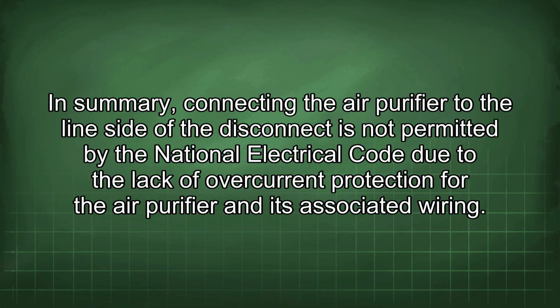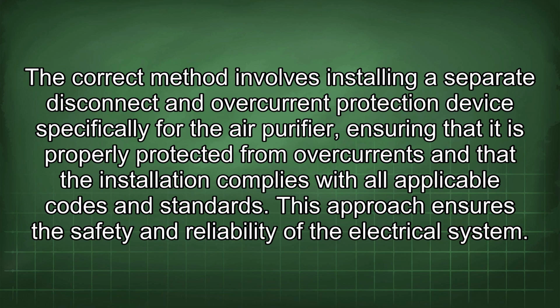In summary, connecting the air purifier to the line side of the disconnect is not permitted by the National Electrical Code due to the lack of overcurrent protection for the air purifier and its associated wiring. The correct method involves installing a separate disconnect and overcurrent protection device specifically for the air purifier, ensuring that it is properly protected from overcurrents and that the installation complies with all applicable codes and standards. This approach ensures the safety and reliability of the electrical system.